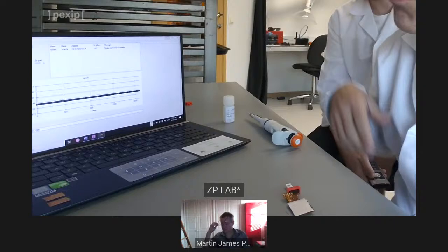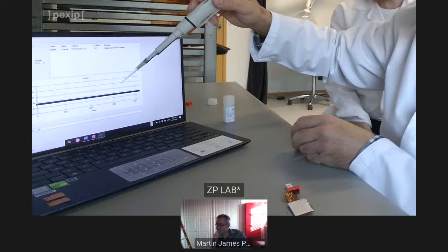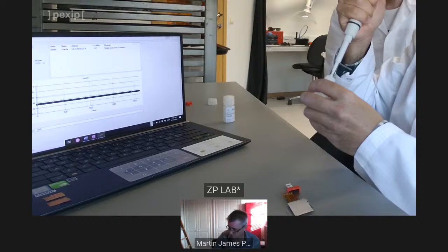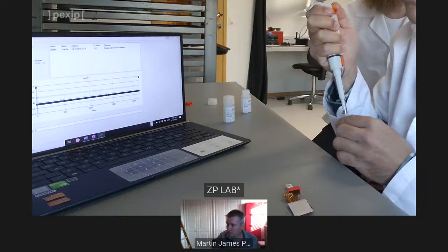The red part is a 3D-printed adapter to hold the sensor in position. I'm going to take two different glucose calibration solutions. It's already communicating — running at a potential of 650 millivolts with a sample rate of five seconds. I should note I don't have control over the scale on this readout platform, so it might be sometimes hard to observe. Andre can read off the numeric value so you can see if there's a step change.